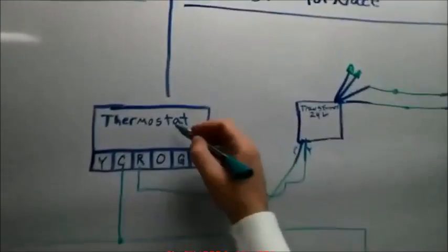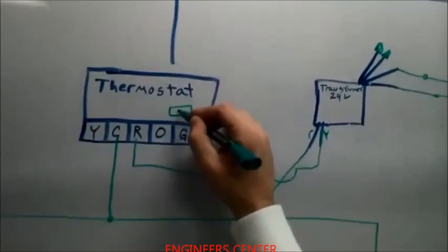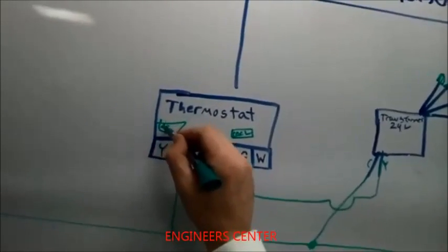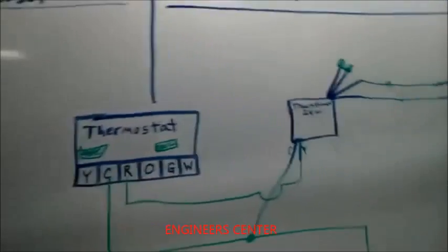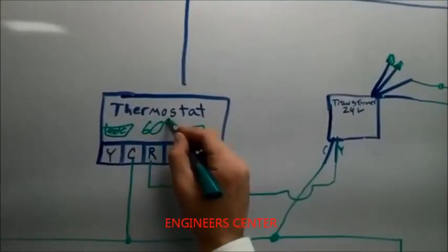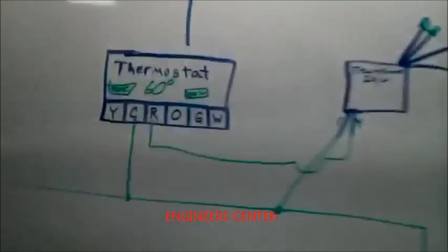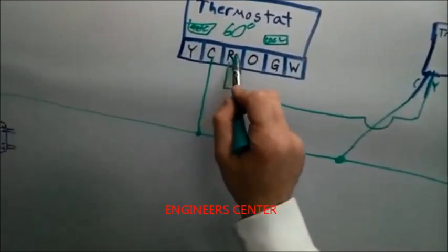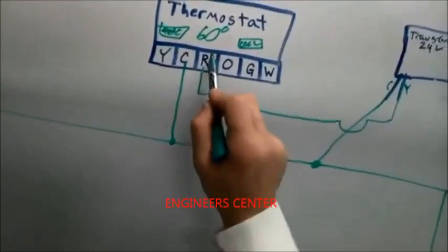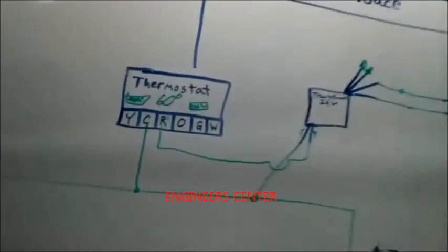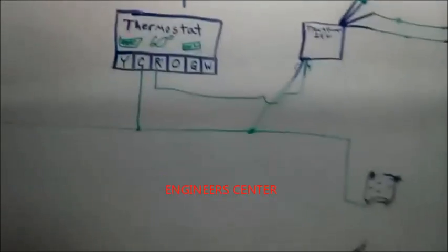Now, when you have a demand for cool, you flip the thermostat to cool, set it to auto, and 60 degrees, just so we know it would turn on. What would happen now is it would connect red to yellow and red to green. And so we'd be closed. It's essentially just another relay.